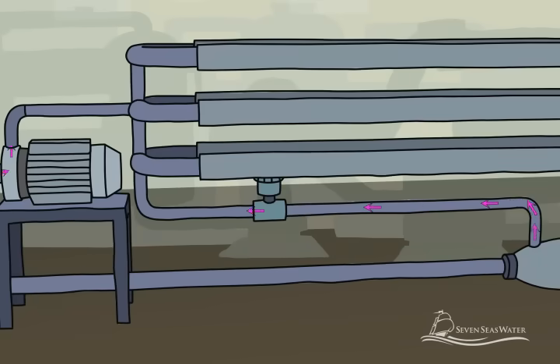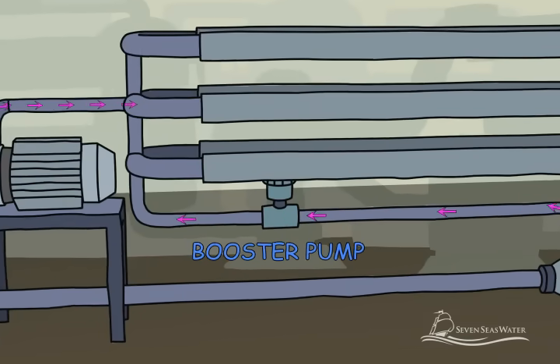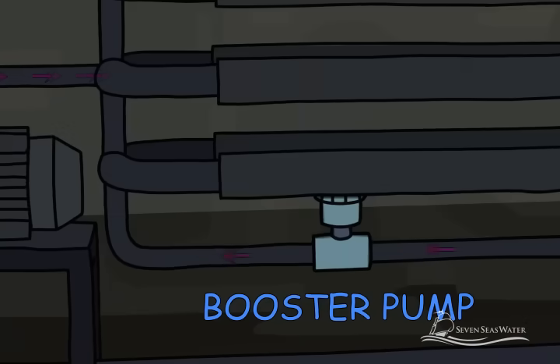The pressurized seawater leaving the energy recovery device has its pressure boosted by a small booster pump so that it is at the same pressure as the seawater leaving the high pressure pump. The boost is necessary as some pressure has been lost as the stream travels through the reverse osmosis system.